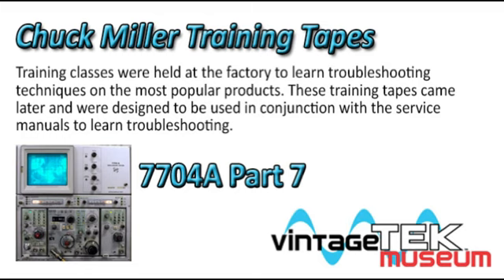To the left is a catcher network composed of CR3103, VR3105, a 15-volt Zener, and C3105. That's to limit a ringing that occurs as Q3102 turns off. There's an inductive kick out of that transformer which would cause a ringing. It is caught and suppressed as CR3103 and VR3105 turn on, connecting C3105 across the secondary of that transformer T3030 and suppresses that ringing.